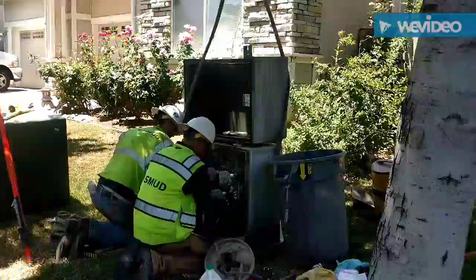Yeah, we have a 6.9 transformer. We have one leg coming in, one leg coming out, and it's feeding 120, 240 to the houses. And there's about 8 homes that are out of power right now that we notified for. This transformer is a 50 kVA transformer. And you can see there's oil on the side where it's leaking, and you can see where it's rusting on the inside. And once that oil pressure gets low, then the transformer will get hot, it'll fail. So we're putting in a brand new one. Our guys have de-energized it. They proved it dead. And now we tape the secondary legs to make sure we don't mix anything up. Going through all of our safety precautions, and we'll be ready to change it out.